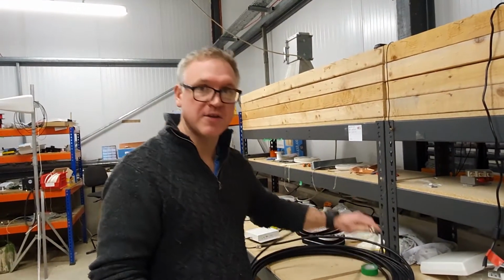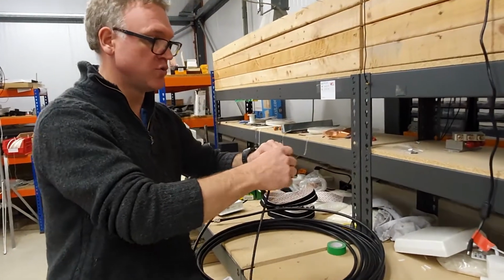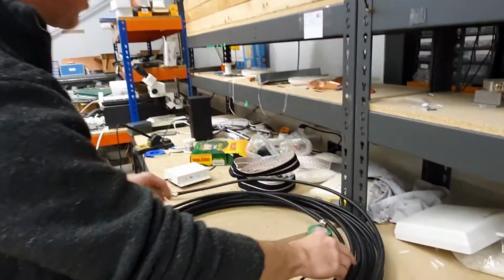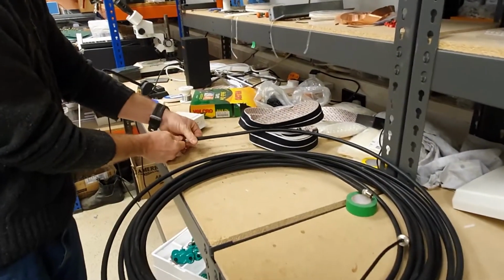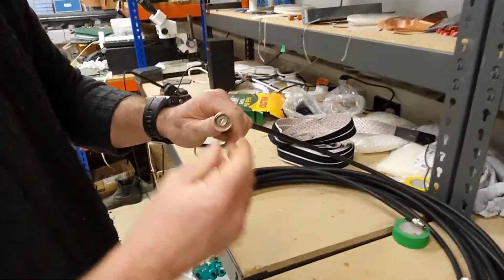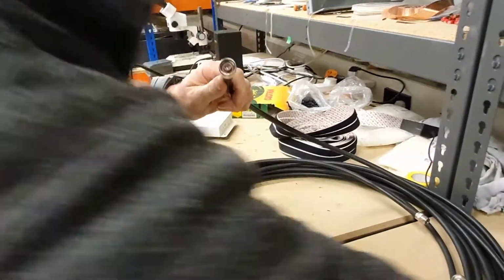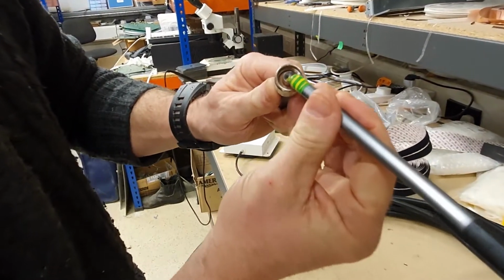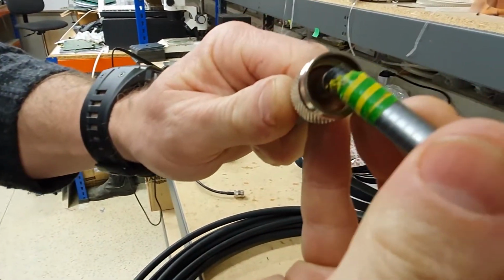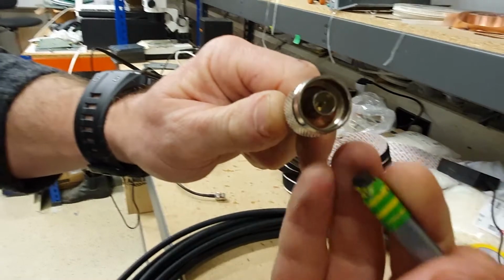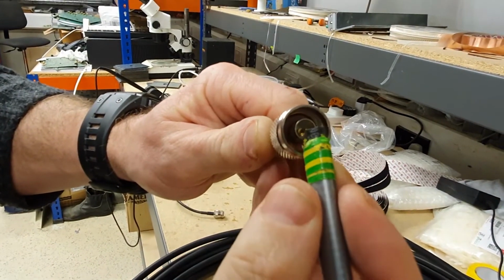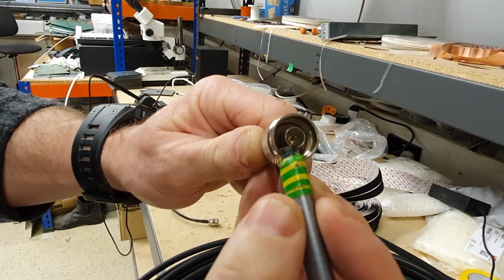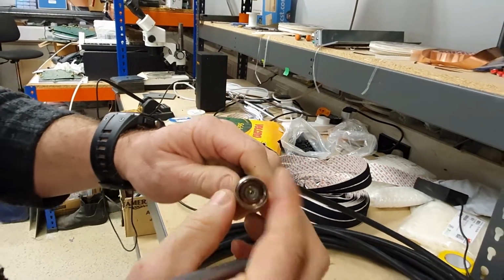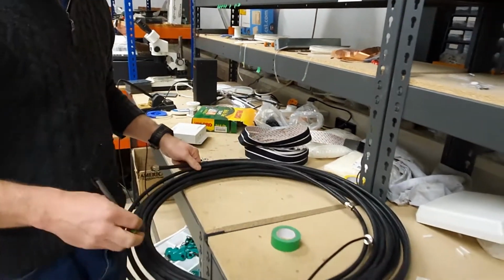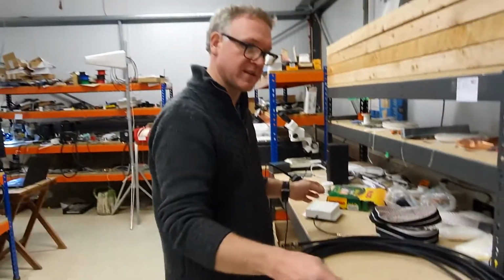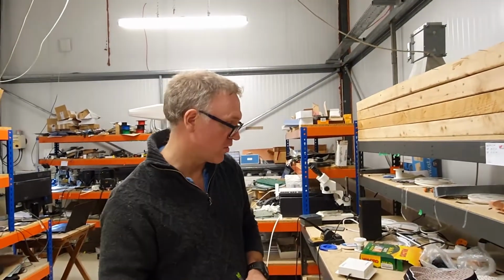And from our experience, that's mainly due to these connectors that are put on, typically these N-type male connectors here. What we typically see when we visit buildings is that the inner connector is too far inside, or there could be a braid of metal that's crossing from that inside connector to the outside part here. And this can typically result in attenuations. So that's the whole point of this cable testing equipment, is to ensure that all your cables are good.